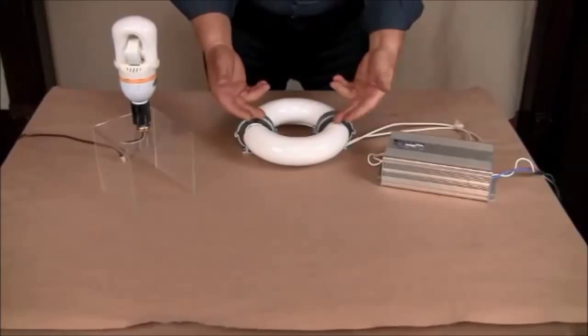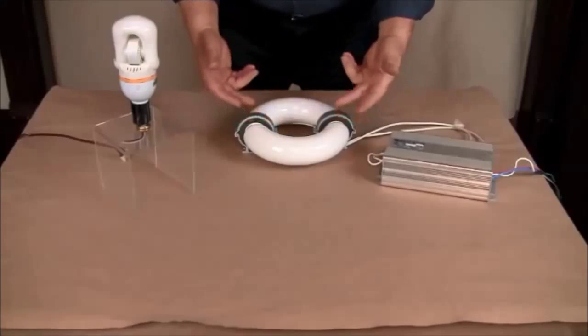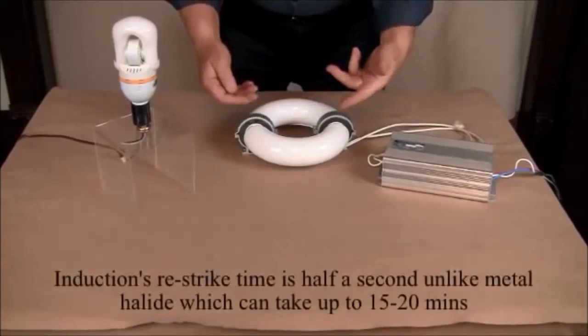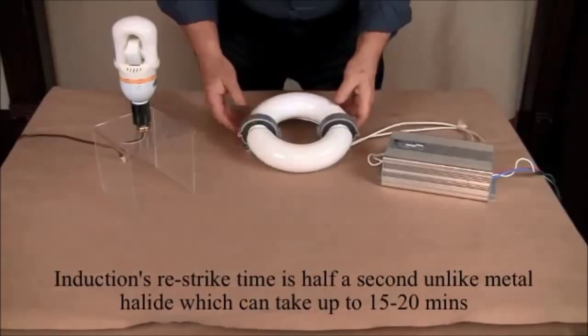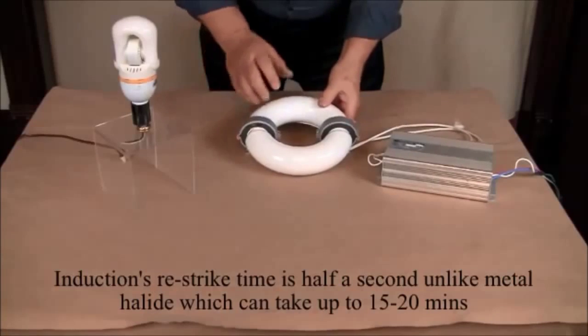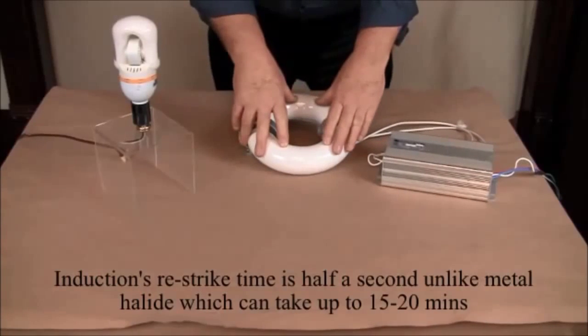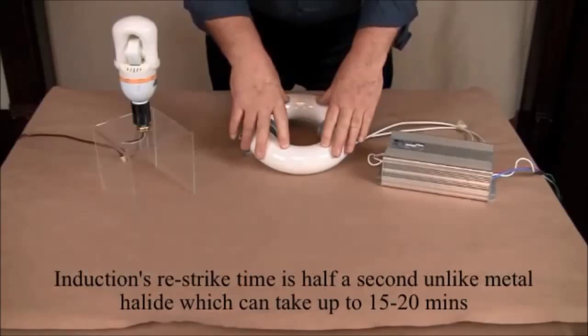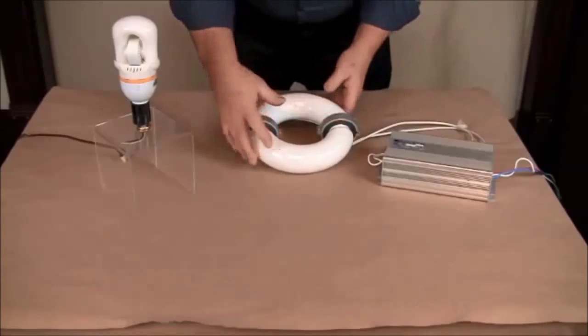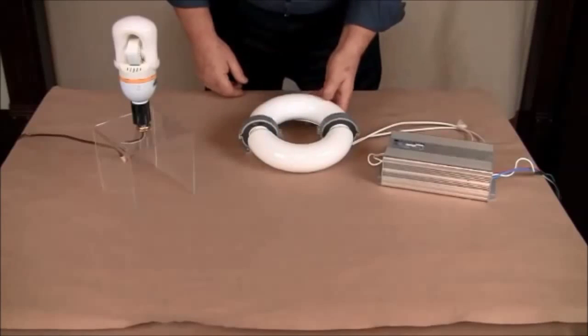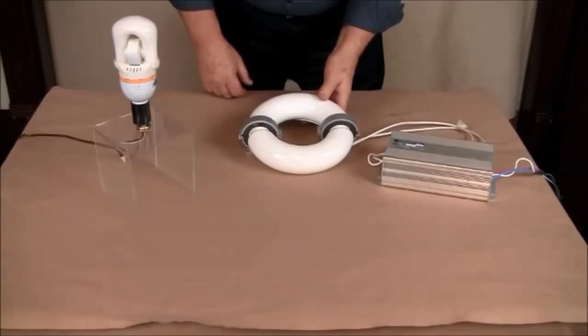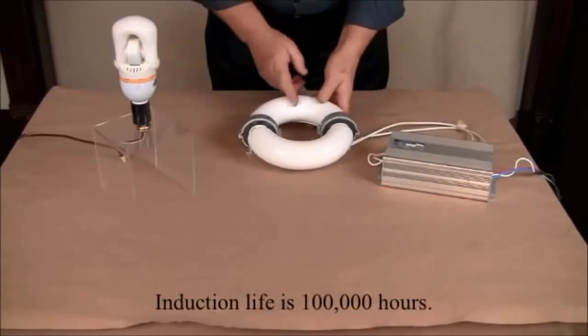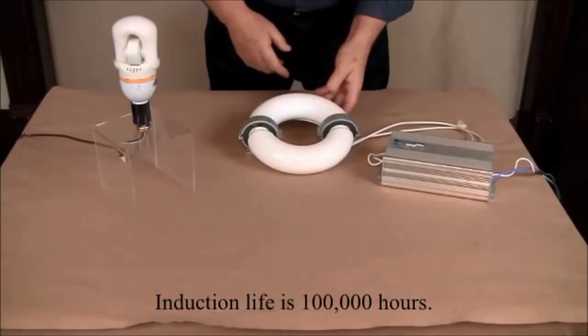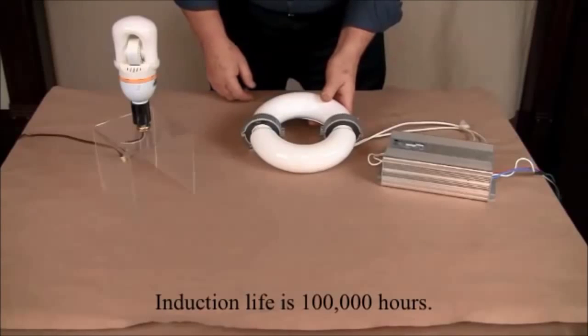Unlike fluorescent lights, you have no electrodes inside the bulb to wear away. Different from metal halide, the restrike on an induction light is half a second, not 15 or 20 minutes when your metal halide lights go out. And again, the life of this tube is 100,000 hours.